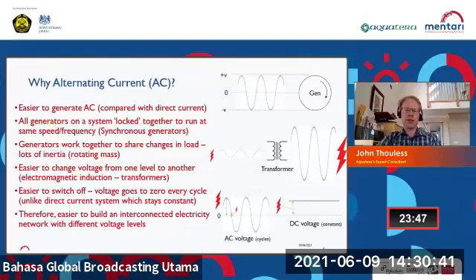If we've got lots of generators, which we have with coal-fired generation, we can lock them together so they all rotate and lock onto that same waveform. That's why we call them synchronous generation, and why conventionally in power systems we like this type of generation, because all the generators are locked together. They follow the same waveform, at the same voltage and frequency, with a lot of rotating mass.